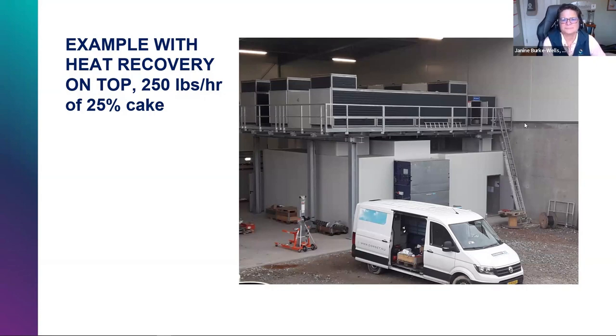Question: how do you demonstrate the material meets Class A time and temperature requirements via controls or instrumentation? There are quite a number of temperature sensors watching the inlet and outlet air in many locations, and the belt speed is known so we know the time the material spends at temperature. As part of the proven process, we also embed small temperature sensors directly in the sludge and track the location, temperature, and time plot of each sensor.